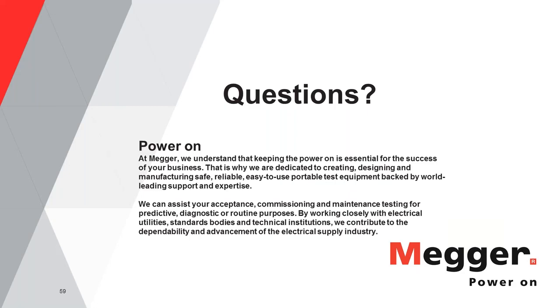I guess Sanket appropriately answered that question. I just want to add one more point: what the question is asking is something that is being done out in the field all the time, because the amount of current that you can get from any given instrument may not be enough for you to test at the trip settings of that breaker. So it is quite common for people to do what you're asking, and it has been industry practice that it is acceptable. But as Sanket mentioned, the ideal scenario would be to test at the trip settings or close to it. But what you are trying to do is something that is accepted by industry.